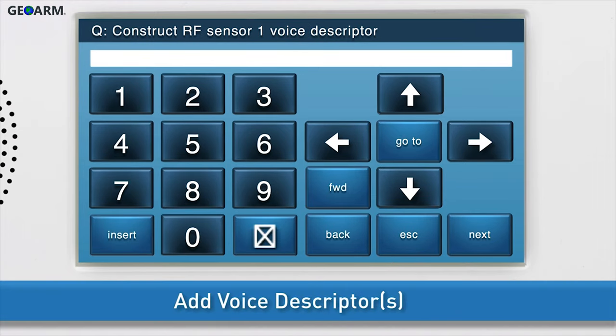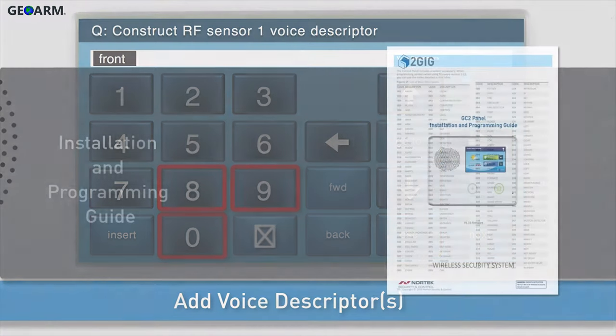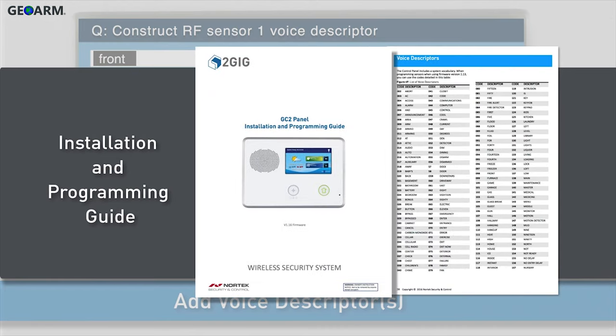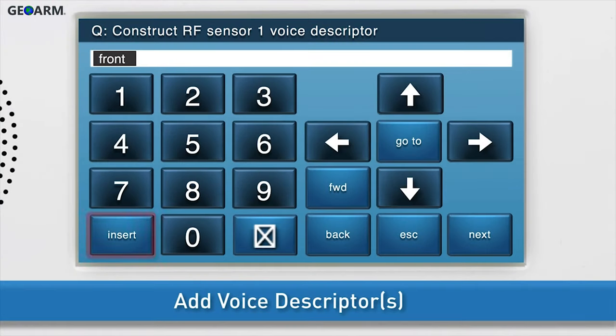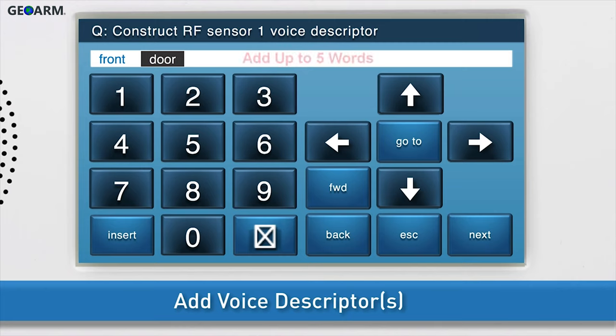Next, add the voice descriptors. Press Insert. The word abort will automatically appear in the answer box. Change the word by either using the right and left arrow buttons, or by typing the word's three-digit code using the keyboard. For a list of all voice descriptors and their associated codes, see the Installation and Programming Guide. To add another word, press Insert again and repeat the steps just discussed. You can add up to five words. Once the desired word or words displays in the answer box, press the down arrow to go to the next sub-question.